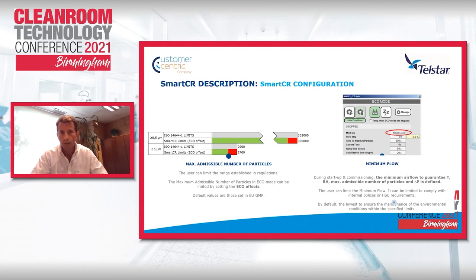There are other parameters, like the eco offset in terms of the two particle sizes that we are measuring. We obviously don't fix the setpoint on the regulation limits, on the ISO limits, but we give a safety margin here. So what is in green will be the eco mode working range, and the red part will be the buffer we have to react and never be above the ISO limits. And as I said before, at the end of all the trials, we will have the minimum flow set and qualified.